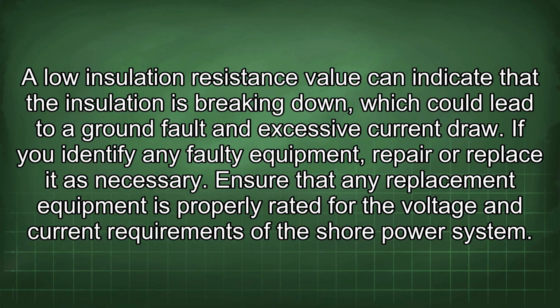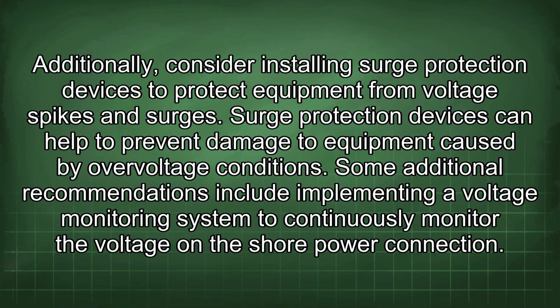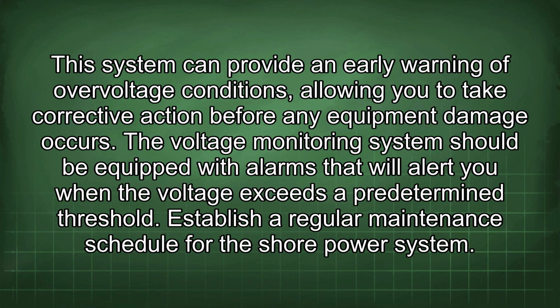Ensure that any replacement equipment is properly rated for the voltage and current requirements of the shore power system. Additionally, consider installing surge protection devices to protect equipment from voltage spikes and surges. Surge protection devices can help to prevent damage to equipment caused by overvoltage conditions. Some additional recommendations include implementing a voltage monitoring system to continuously monitor the voltage in the shore power connection.